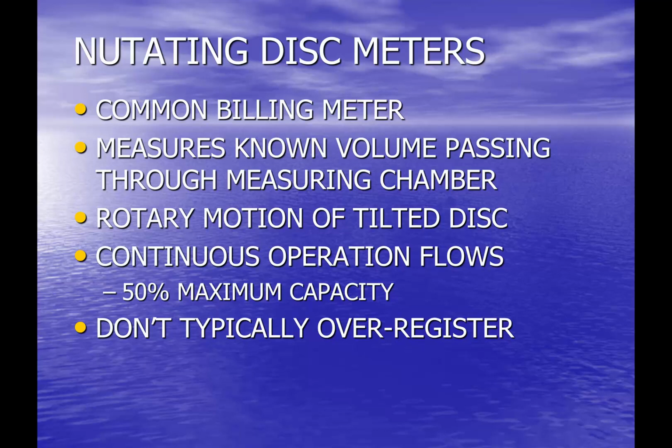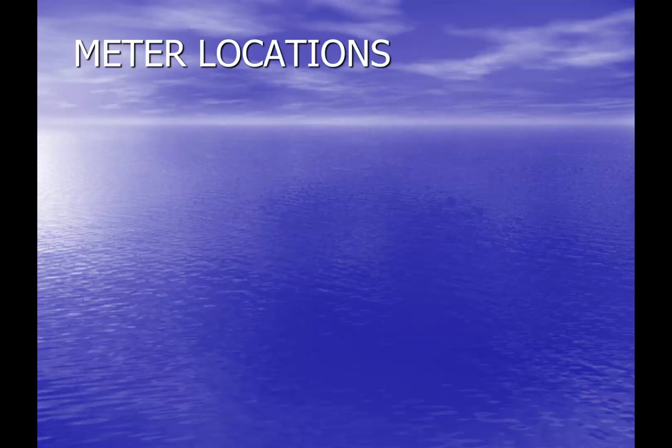Those that kind of say, hey, your meter's got to be the problem, you should replace the meter, tend to be surprised when what really happens is their bill goes up, because the likely problem with a meter that's older is that it's not reading all the flow, and when you replace it, you actually start capturing all that flow, and their bill increases, and then they get all uppity. The explanation simply is, hey, you were getting away for a while without paying for all your water. Now we're asking you to pay for it, which is always an interesting conversation.